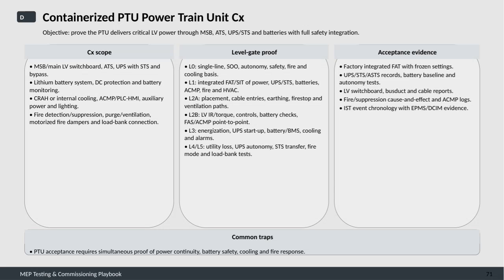This slide focuses on the testing and commissioning of the Containerized Powertrain Unit, or PTU, highlighting the key areas we need to verify to ensure it functions safely and reliably. The main objective is to prove that the PTU delivers critical low-voltage power through the main switchboard, automatic transfer switches, uninterruptible power supplies, and batteries, all while integrating full safety features.